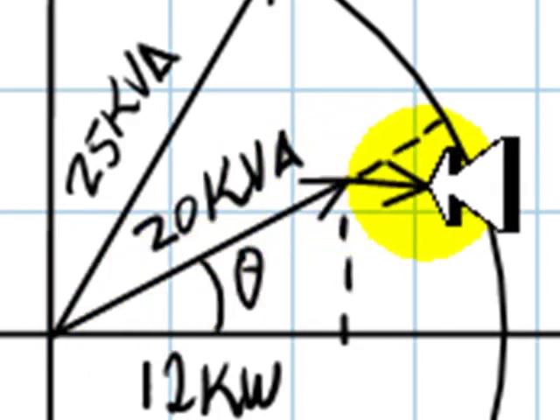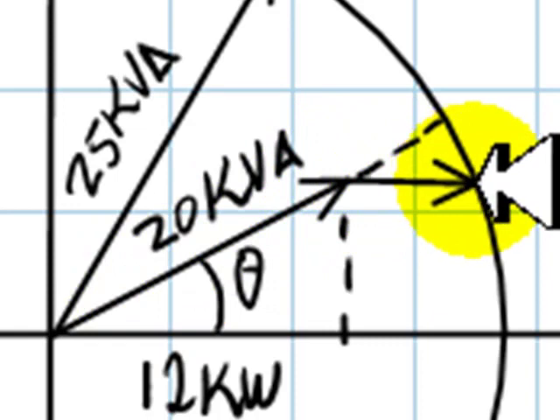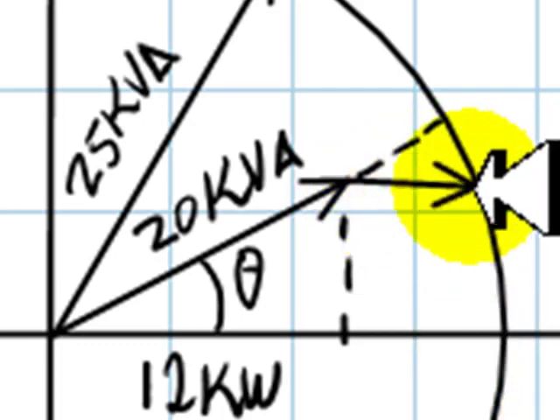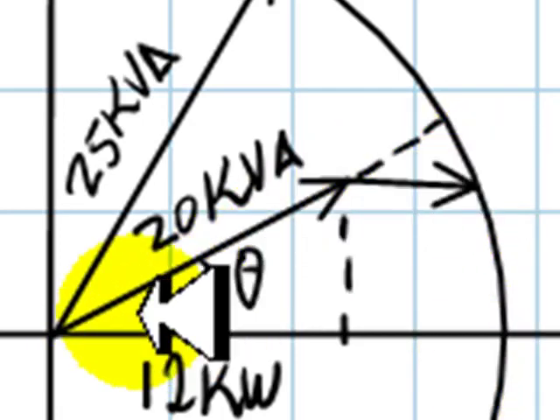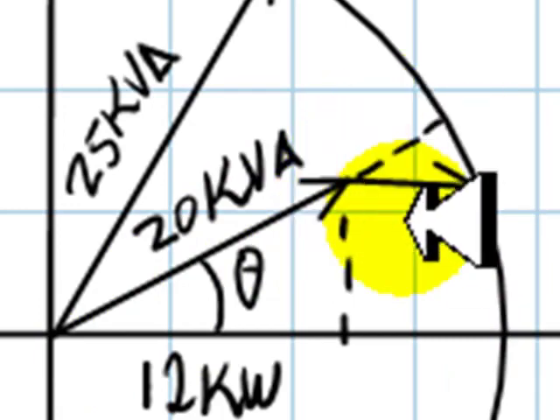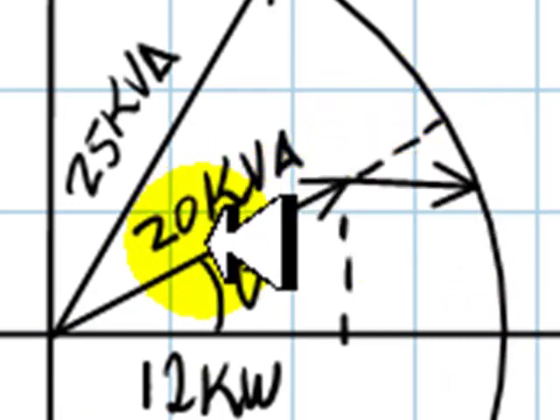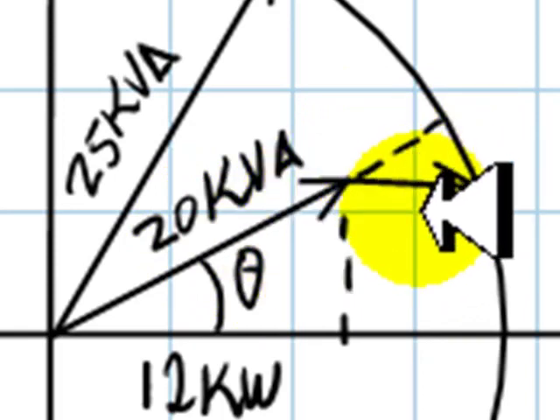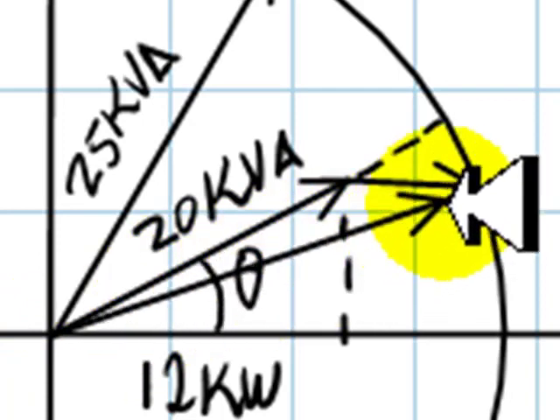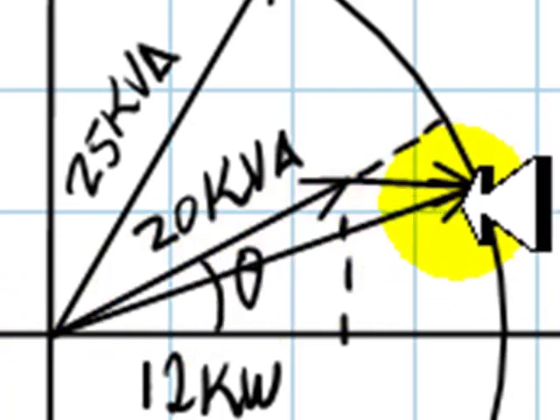So the extra load is going to be drawn horizontally because it's only resistive, it's only active power. I don't know how much it is, but one thing I know is that when we add them together, the new load plus the old load of 20 kVA, the total load is going to be 25 kVA, the full load capacity of the transformer.